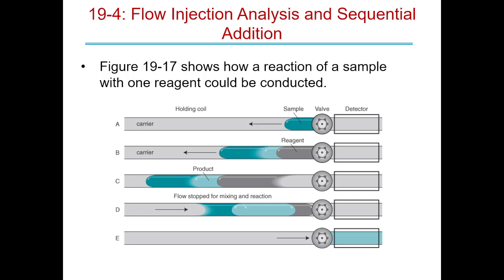And this is why it's referred to as a holding coil, because you'll inject both of these, and then you're going to hold those for a bit, okay? And then what you're going to do is reverse flow. And once you reverse flow, this six-way valve is going to move to the detector now, and that's going to let this back through to the detector. And notice you'll have product in between these two because those are the only places this is, right? Cool, huh? Isn't that beautiful?